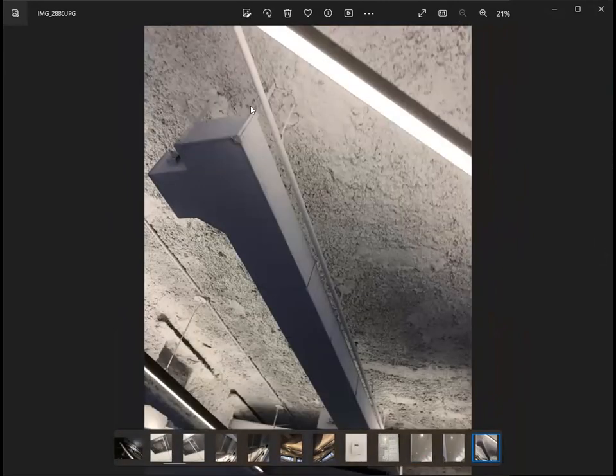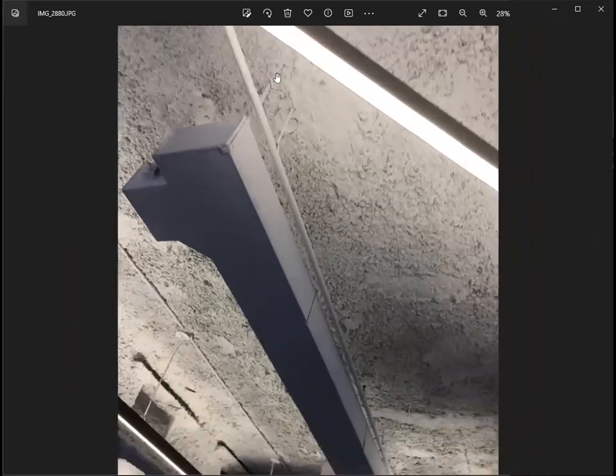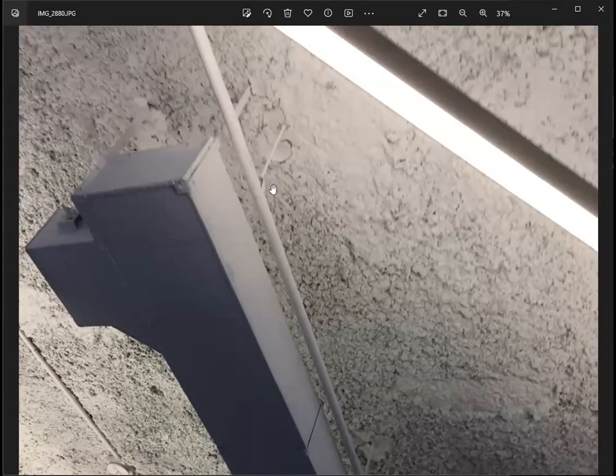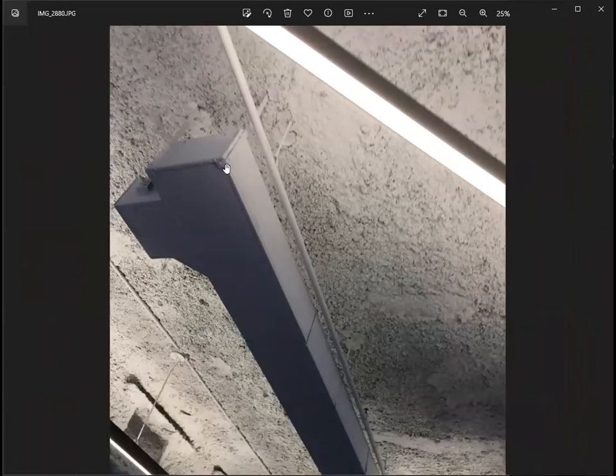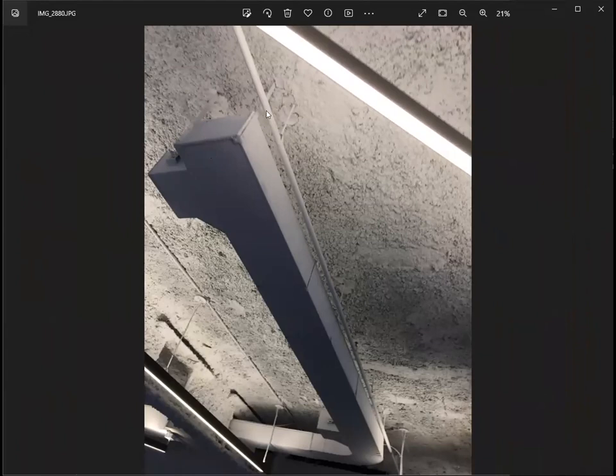And ductwork, if it's a new ductwork, they have penetrated the existing rated ceiling, so they have patched it with approved patching material, fireproofing material. And this ductwork should have a minimum hanger support, and even the pipe. This is a sprinkler pipe, so it depends on how big the ductwork is and how big the pipe is. So at least minimum, you could say every 6 feet should be probably safe to have a hanger support. This will be ductwork inspection. You will fall on the mechanical system inspection.